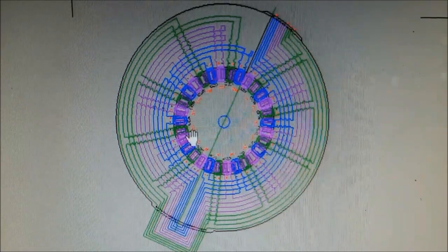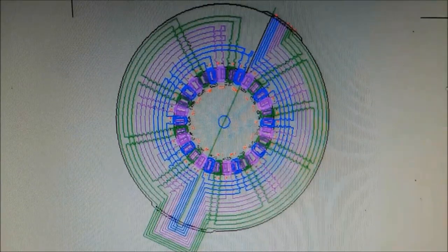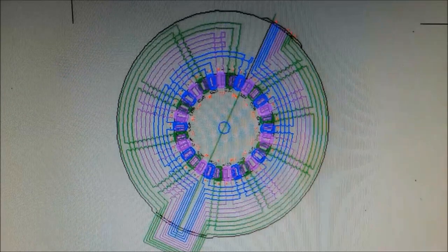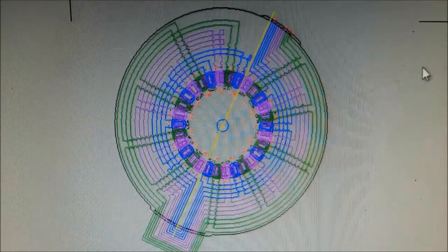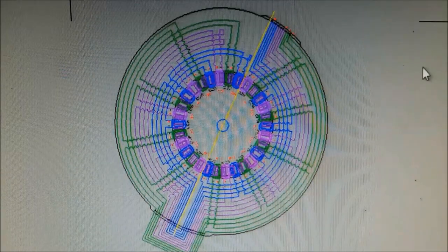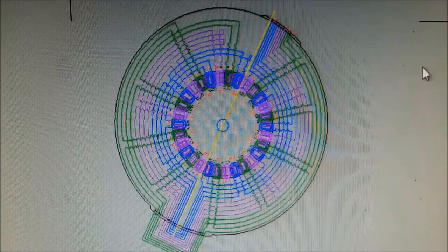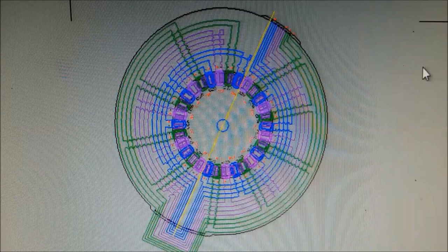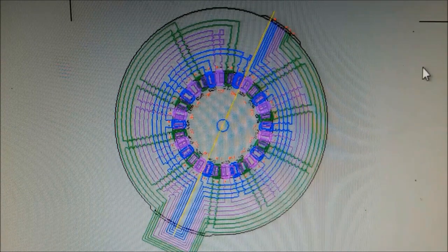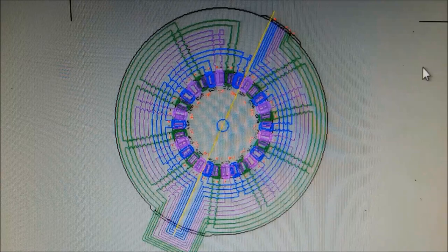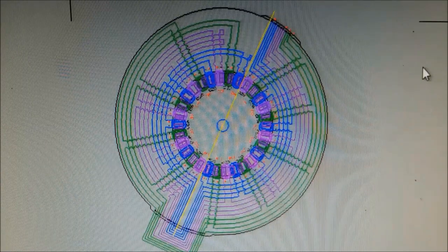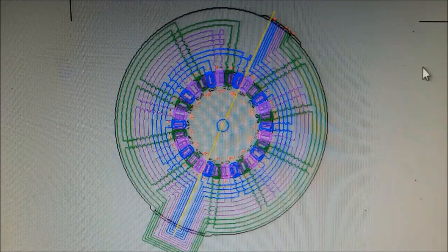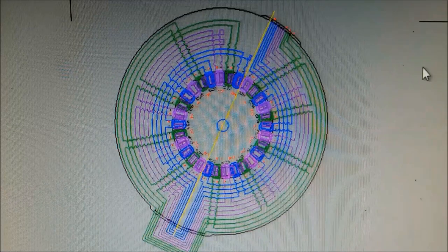First change that you won't see very often. This line across here, this stator is being built in two halves, a left half and a right half. That's because the magnets on this motor pull around 11,500 pounds towards each other if they're at three quarter inch spacing. That's dangerous to be around. You don't want to assemble and disassemble that half a dozen times. So once we get it running true with a dial indicator, we don't want to mess with that.